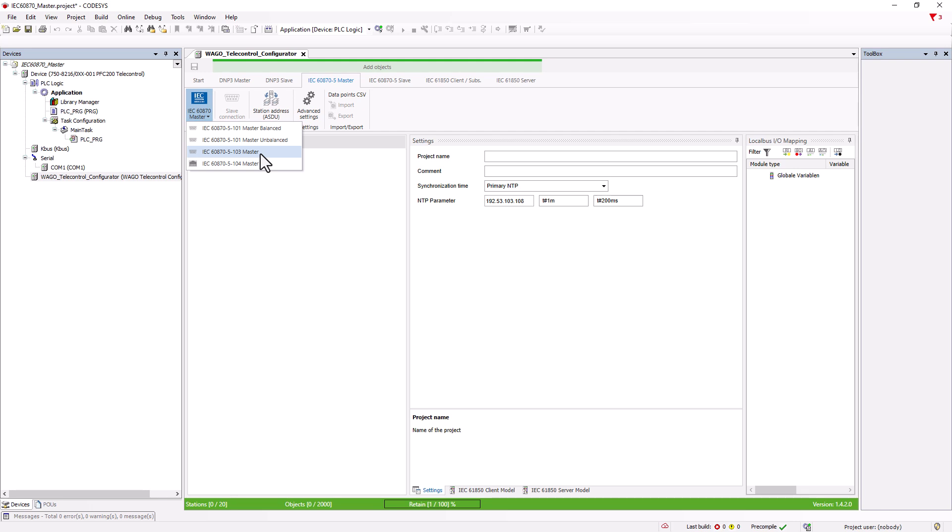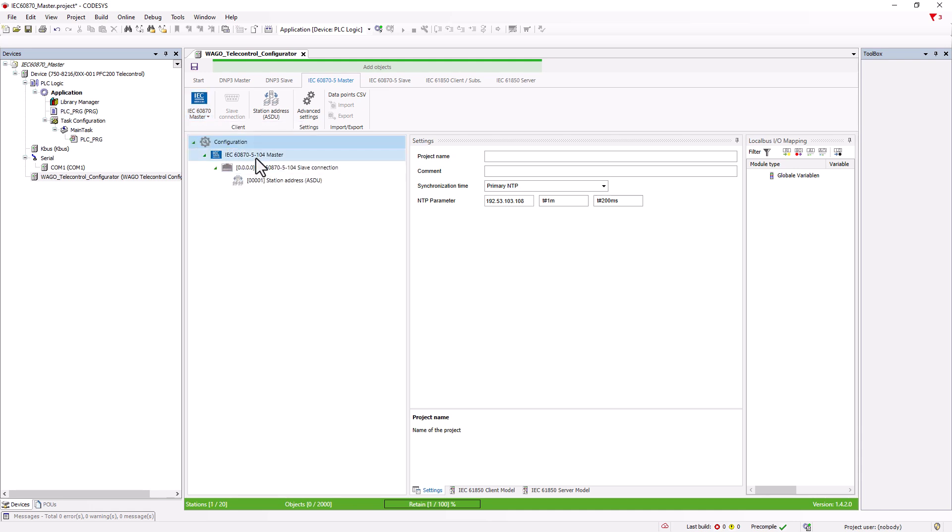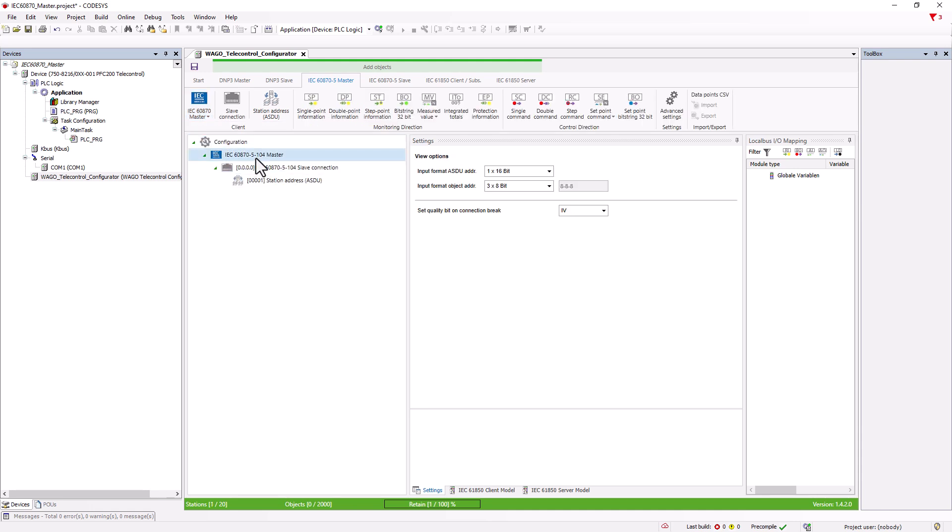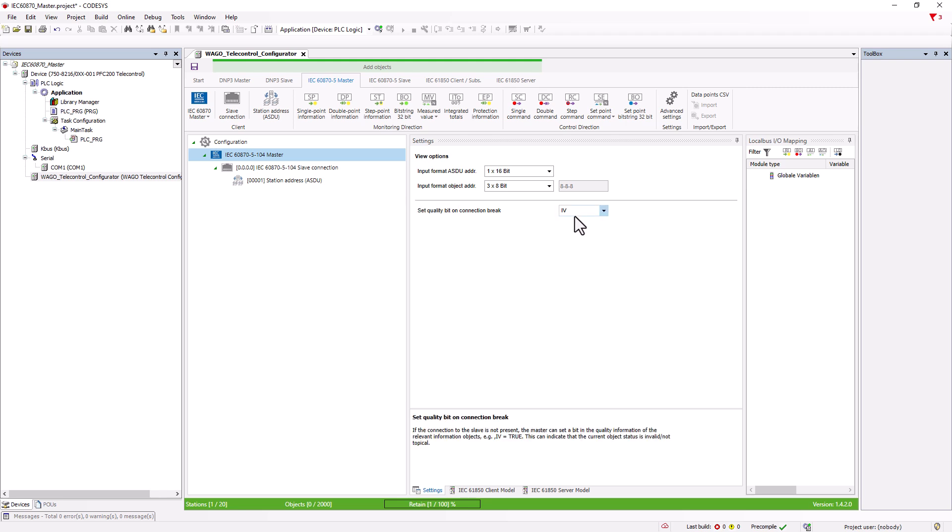We start with the IEC 60870-5-104 protocol that communicates over the Ethernet interface. Most of the general settings have already been described in detail in the IEC 60870 slave tutorial, a link to the video can be found in the video description. There is an option to set an IV or NT bit when communication with a slave is lost to mark the affected information objects as invalid or out of date.